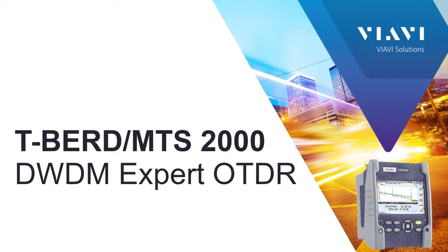Viavi's E41 DWDM-C OTDR module allows you to characterize, turn up, maintain, and troubleshoot DWDM metro access networks. While most of our standard OTDR modules operate at 1310 and 1550 nanometers, the DWDM OTDR operates at wavelengths defined by the ITU-T G.694.1 frequency grid with channel spacing of 50, 100, and 200 gigahertz. It is the right tool for DWDM metro access network construction, upgrade, and troubleshooting.